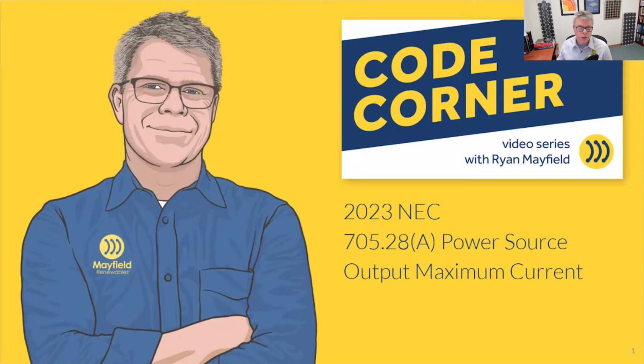Today, we're going to focus in on the 2023 NEC, and specifically look at 705.28(A), talking about power source output maximum current. So 705 is about our interconnections, interconnecting multiple power sources. The way that we use it a lot in our PV systems is our PV systems getting interconnected with the utility. Could be a battery system connected with the utility, could be other sources, doesn't have to be restricted to those, doesn't have to be utility even. So we are connecting multiple power sources together, and that's what we're going to be looking at.